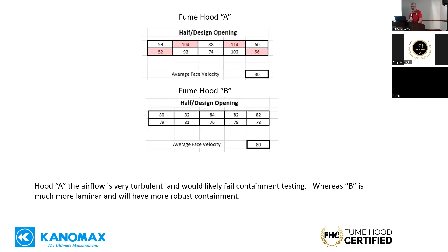It doesn't totally replace full testing, but it is a good way. And one of the interesting things is that most everybody that owns a fume hood is in a position to buy a monitor, airflow, a hot wire anemometer. And with that, that's all you need to do your own face velocity profile. So, what we recommend is get the hood tested. They're going to give you a face velocity profile, and then you come back yourself every couple of months or whatever and redo that, because it takes 10, 15 minutes, and then you'll know if the hood is staying where it was or if it's drifted off.